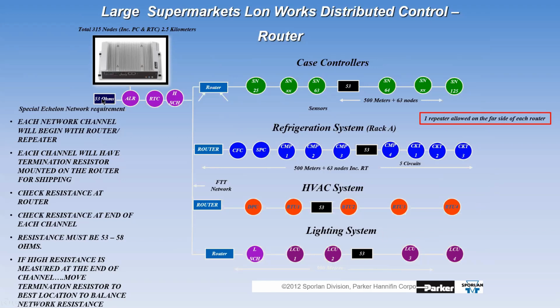What we do is put a 53 ohm on the backbone, and for every network segment or channel, we put another 53 ohm somewhere close to the geographic middle of the network. What we're doing is making sure that the backbone and every network channel are both balanced - they both have an intrinsic resistance of 53 ohms. That acts as a shock absorber and helps the system communicate.